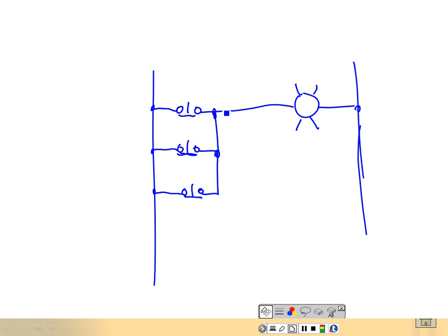And what would be required to turn the light off? All. Not any, all. They're normally, yeah, they're all normally closed. By the way, sometimes it gets hard. And this is what you need. If the line is drawn above, it's normally open on push buttons. If the line is drawn below, it's normally closed. Whether I accidentally don't touch it or not, if it's below, it's normally closed.